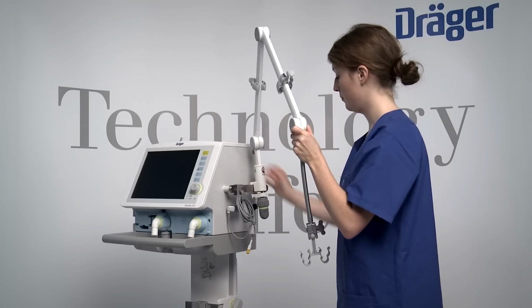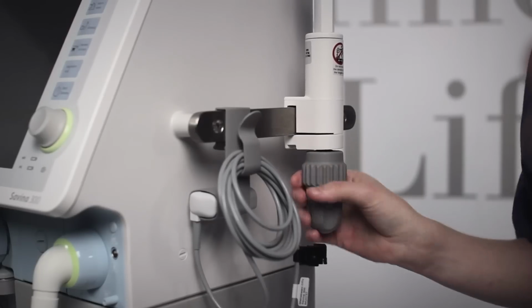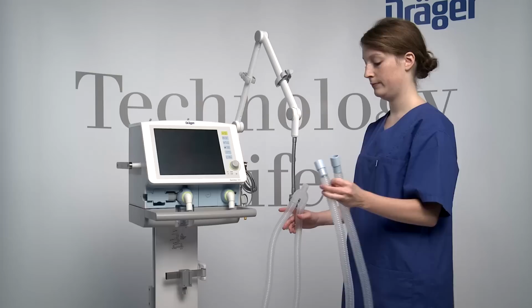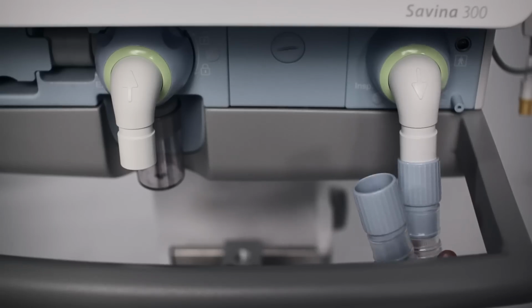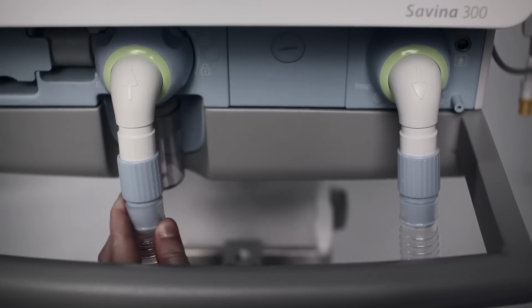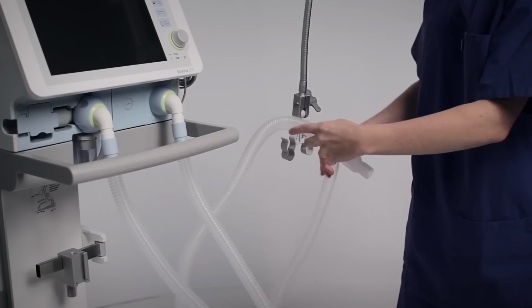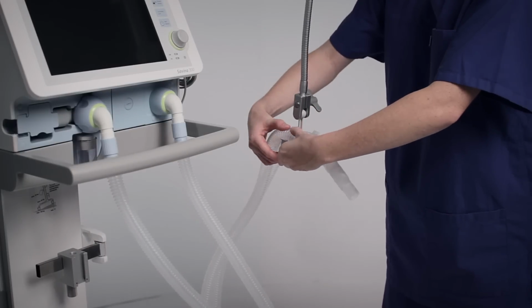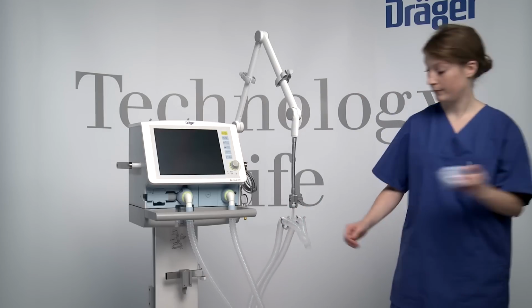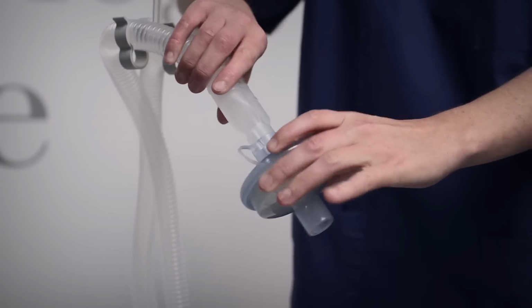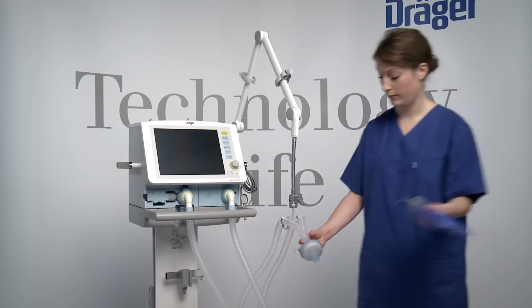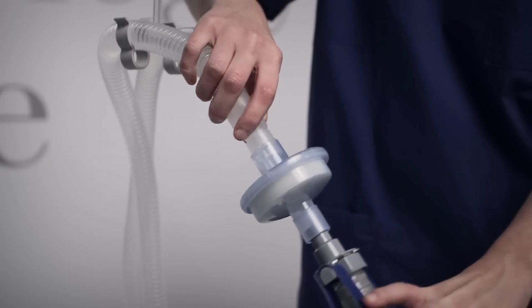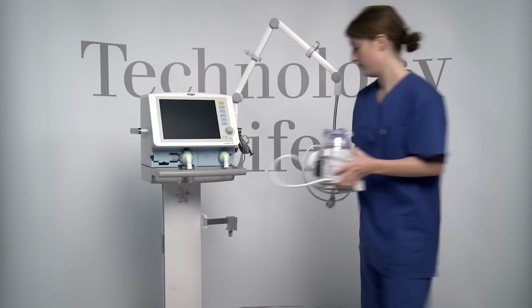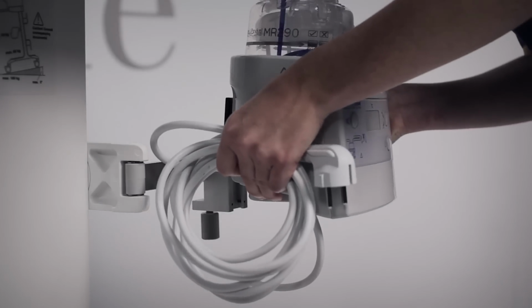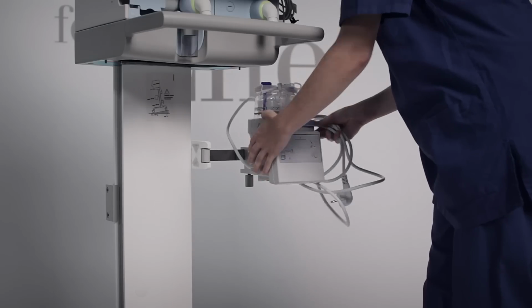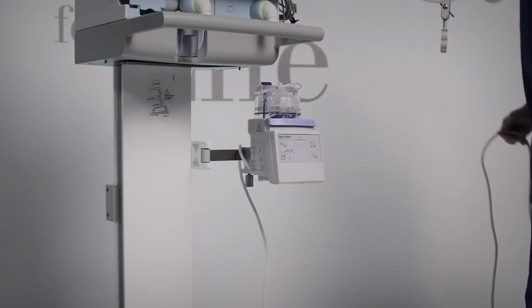Hang the hinged arm on the lateral standard rail of Savina 300 and tighten the screws. Connect breathing hoses to the inspiratory port and to the expiratory port. Insert the breathing hoses in the opening of the hinged arm. Then the HME on the Y-piece. And the test lung on the HME. If no HME is used, a breathing gas humidifier should be installed on the humidifier holder for breathing gas humidifier.